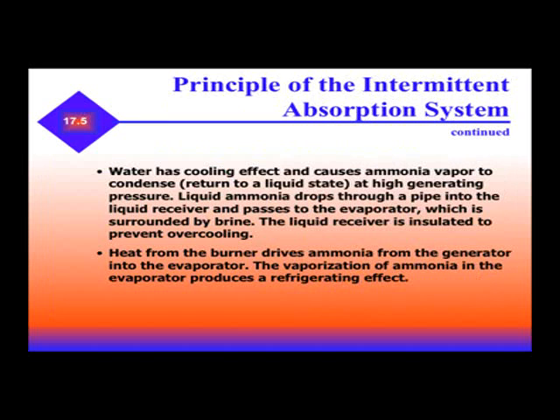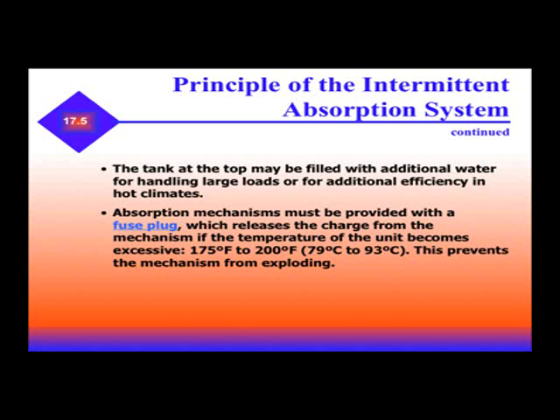The liquid receiver is insulated to prevent overcooling. Heat from the burner drives the ammonia from the generator into the evaporator. The vaporization of ammonia in the evaporator produces a refrigerating effect. The tank at the top may be filled with additional water for handling large loads or for additional efficiency in hot climates. Absorption mechanisms must be provided with a fuse plug, which releases the charge if the temperature becomes excessive — around 175 to 200 degrees — preventing the mechanism from exploding.